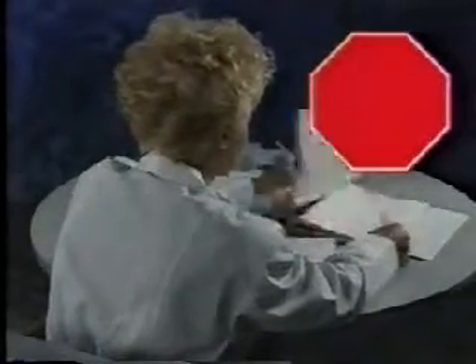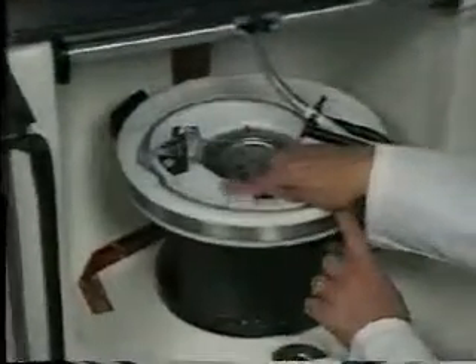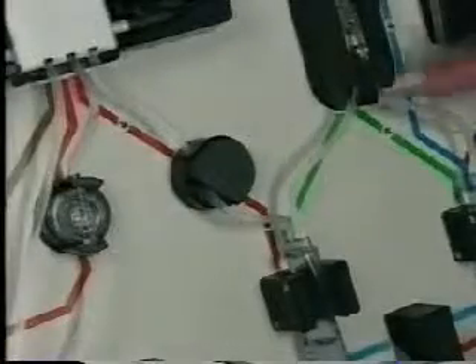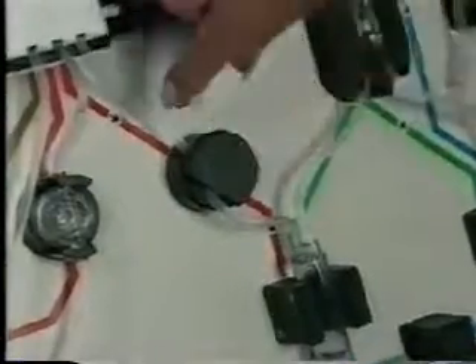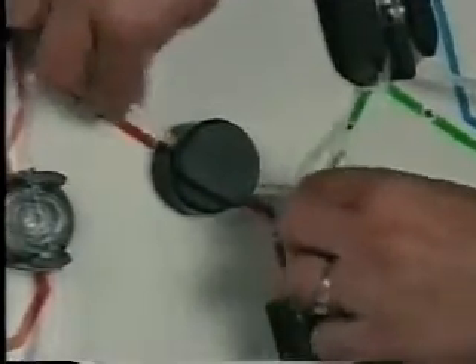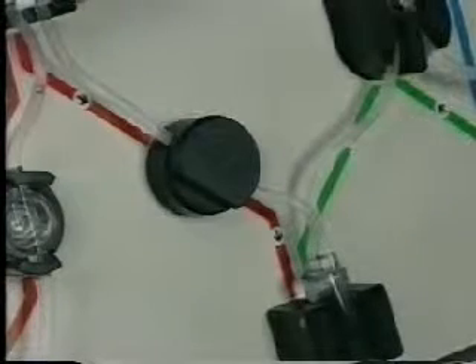Let's review two of the possible causes for the centrifuge pressure high alarm. First, this alarm would occur if there were twisted or pinched lines in the centrifuge. Open the centrifuge chamber, examine all the lines, reseat any loose lines, and close the centrifuge chamber. Press Continue to clear the alarm. If the alarm does not clear, you will need to check the inlet line on the centrifuge pressure sensor. Once you move the line in the sensor, you must reprime the system. To reprime the system, press Change Mode, then select 2 for Prime. Stop the tape and do exercise 8.